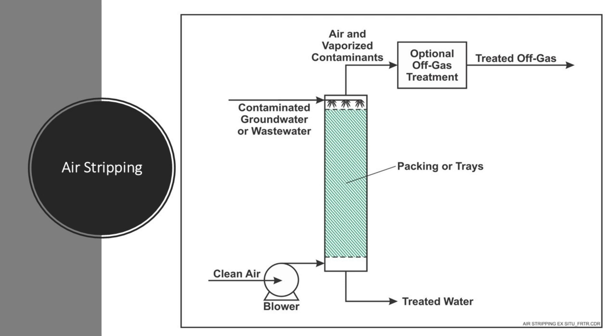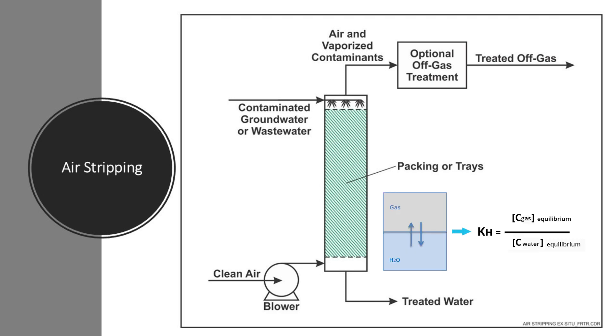The fundamental principle behind air stripping is the difference in volatility between water and VOCs. Volatility refers to how easily a compound transitions from a liquid phase to a gaseous phase. VOCs have a high volatility, meaning they evaporate readily when exposed to air. Air stripping leverages this property through a process called mass transfer, where VOCs move from the contaminated water into the air. This transfer is driven by Henry's Law, which states that the amount of gas that dissolves in a liquid is proportional to its partial pressure in the gas phase. By introducing large volumes of air to contaminated water, the partial pressure difference encourages VOCs to volatilize out of the water and into the air.